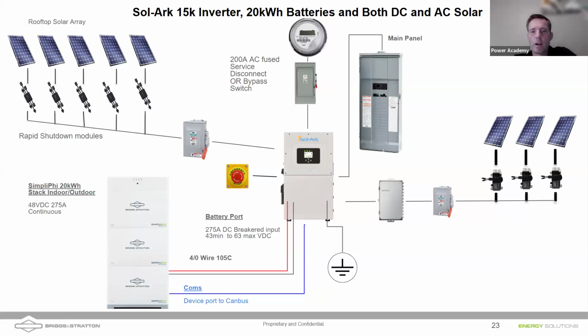This is whole home backup in a grid down situation. Same thing, the DC solar is still alive, but the battery and the inverter are able to grid form, and that'll turn the AC coupled solar on as needed to power the loads and charge the batteries. So this is another example of AC coupling, but we're showing both AC and DC coupling and showing it with a whole home backup with a Sol-Ark 15K.